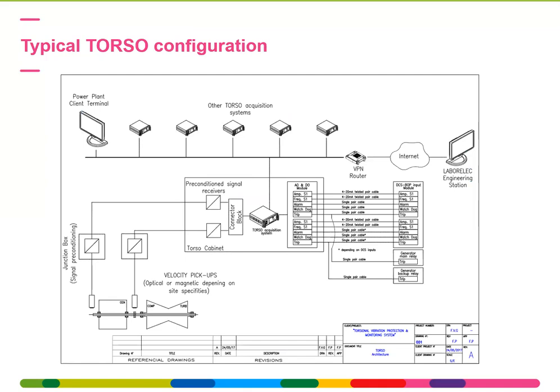The junction boxes with signal conditioning are shown close to the sensors. Typically, these are placed near the machine at, for instance, 5 to 10 meters. And then from these junction boxes, which ensure that any disturbance on the signal is minimized, you go with the cable from the machine room to the instrumentation room. There again, it enters a rack where you have, again, conditioning of the signals and then the acquisition and post-processing. So this is in the torso cabinet and the torso acquisition system.